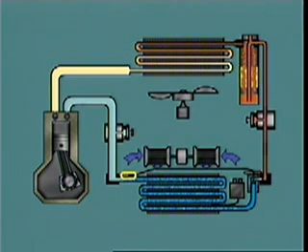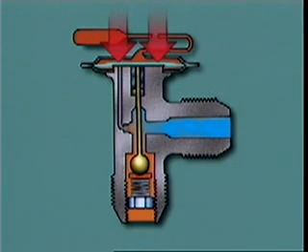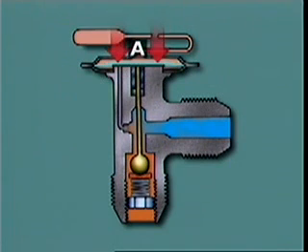The temperature of the refrigerant leaving the evaporator is interpreted by the sensing bulb attached to the outlet. If the temperature is low, the refrigerant in the sensing bulb will contract and pressure in chamber A of the TX valve will reduce. The diaphragm moves and the valve moves towards the valve seat to reduce the quantity of refrigerant entering the evaporator.